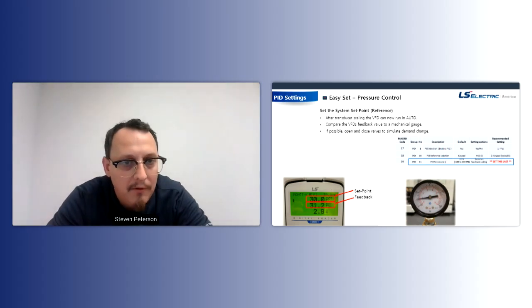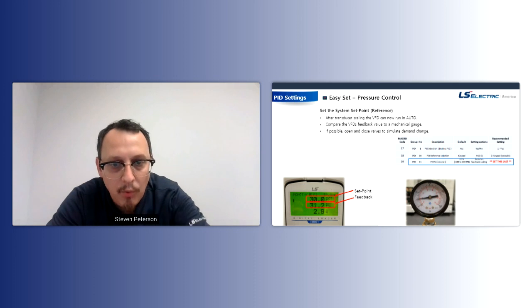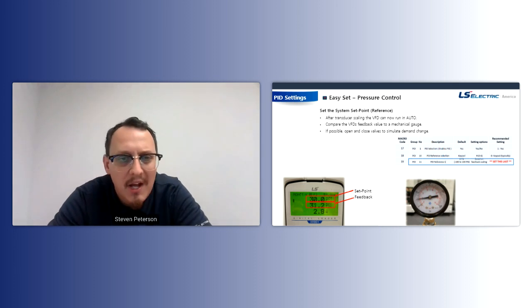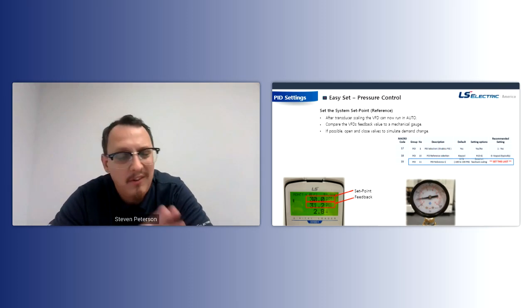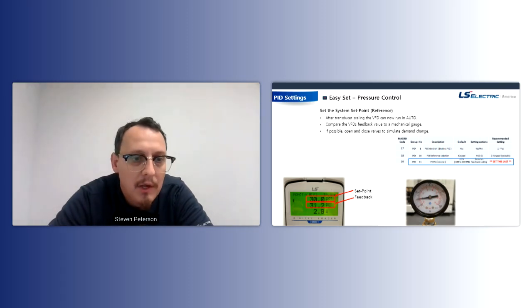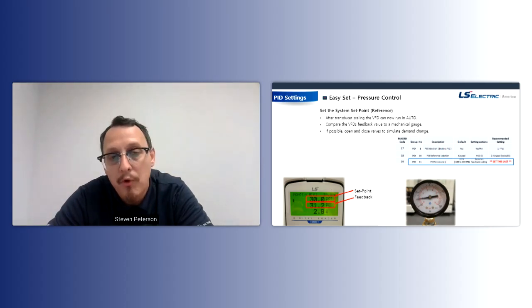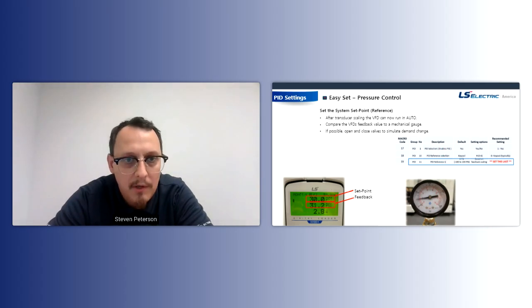This is actually a good time to compare your feedback value on the keypad to a mechanical gauge. I tried to get a couple good pictures here showing, hey, we have a 31 PSI feedback and we're at about 30 PSI on the mechanical gauge. It should be relatively close, within a few PSI. If it's way off and things are acting funny, that's when you want to double check that initial scaling we talked about. Most of the time, guys have 4 to 20 milliamp transducers. Sometimes you have a one-off 0 to 10 volt transducer. So just make sure everything's programmed right for the transducer. That's usually what it comes down to if there are any issues or discrepancies.